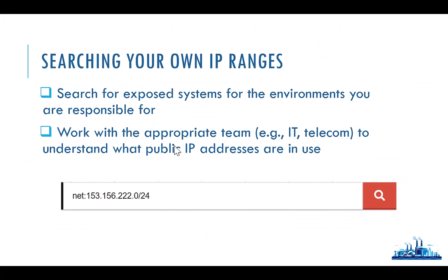You could use this to find exposed systems if you work in a control system environment like a power plant. Work with your network services team to ask what public IP ranges you have, then run a search in Shodan to see what services are exposed. Make sure you don't actually have control systems exposed to the internet, because that's how attackers find a system, take control over it, get a foothold on the control system network, and spread further to take over that power plant, water treatment facility, subway, refinery, open pit mine, or any other industrial control environment — with serious real-world consequences.